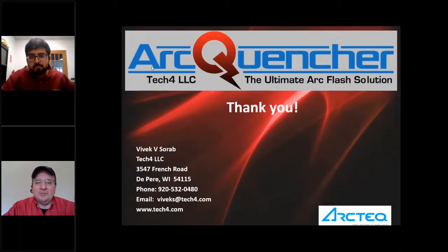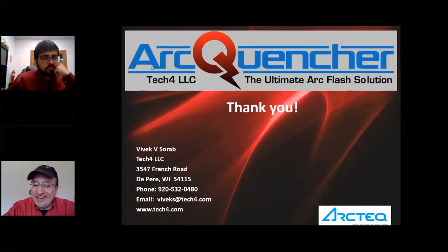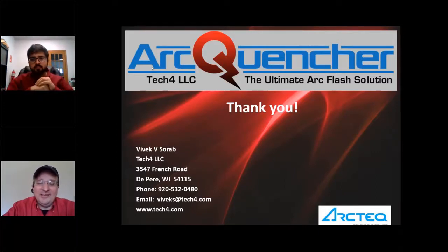I should further add that because someone asked earlier about the Siemens system. The Siemens SiQuench system, as presently designed by Siemens, uses our Arcteq relay, and identical to our Arc Quencher devices, the SiQuench device is asserted not with an electrical signal, but with that fiber optic signal, identical to our own Quencher technology. Now, Eaton, similar to Siemens, also brand labels the Arcteq relay for their low voltage Arc Quencher solution, but the Eaton Quencher is not a resettable device.